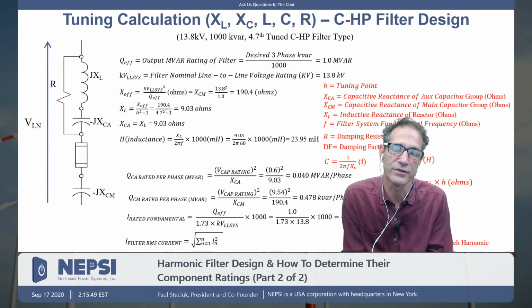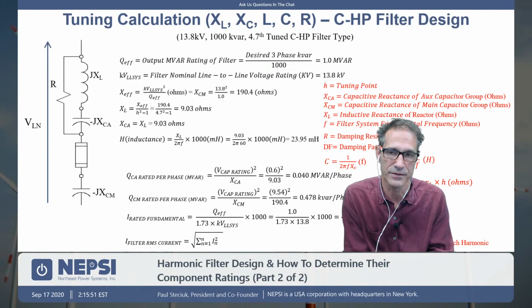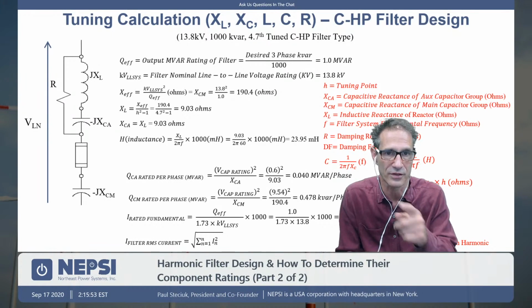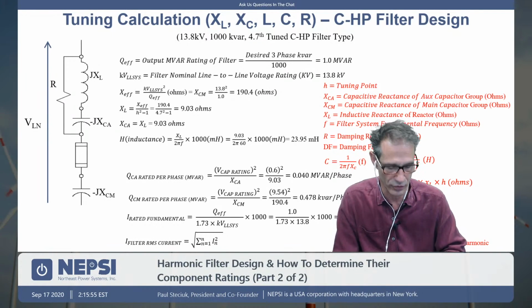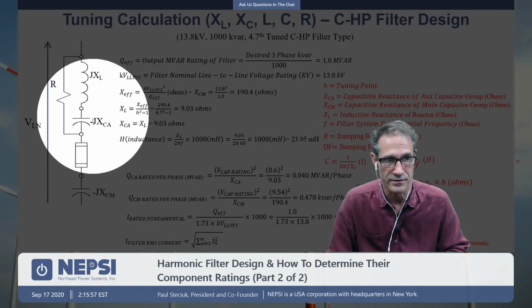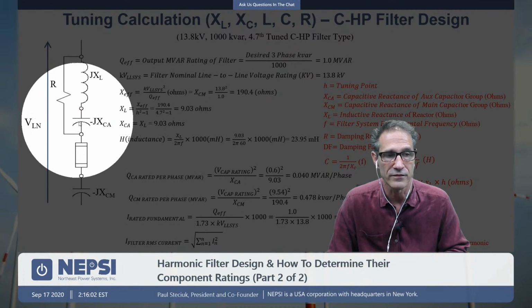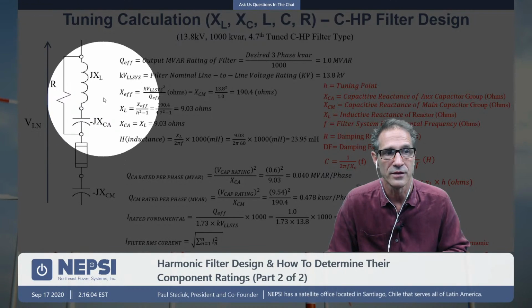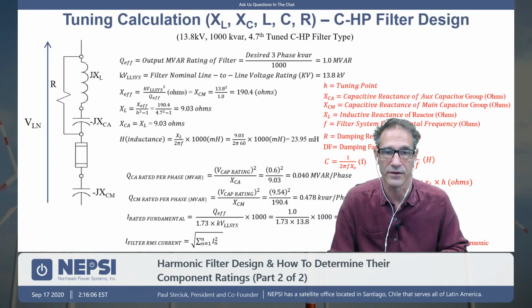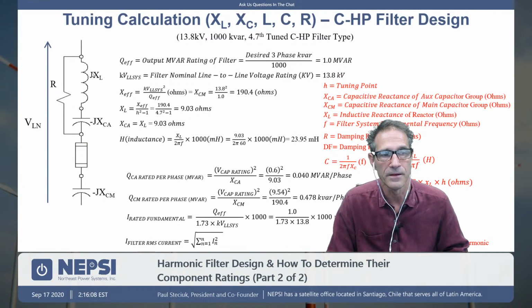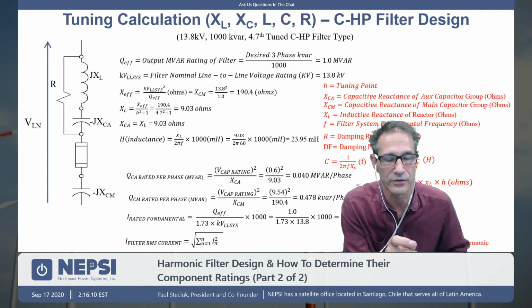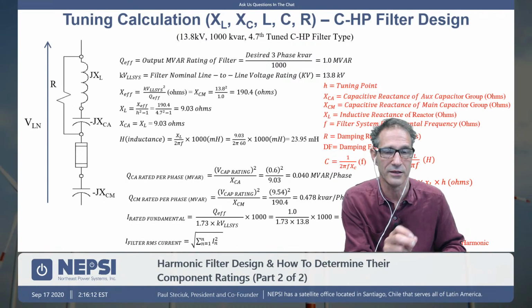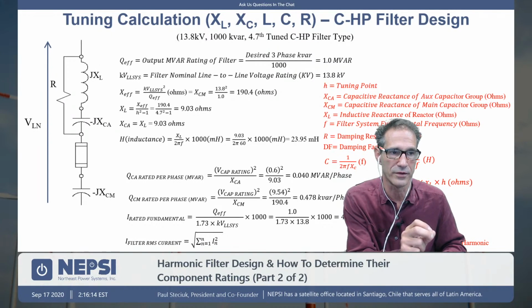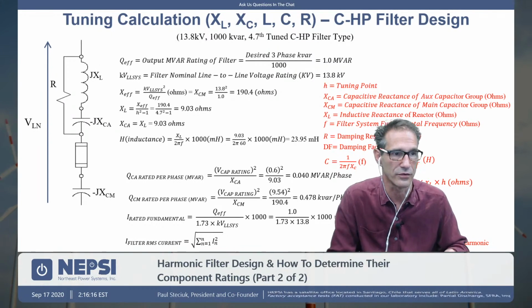C-high pass filters and high pass filters have the same characteristic curve. The only difference is this value of X of CA here. And that value of X of CA is put in place where it exactly equals X of L at its fundamental frequency, not its tuning frequency. So X of CA equals X of L at the fundamental, whether it's 50 hertz or 60 hertz.